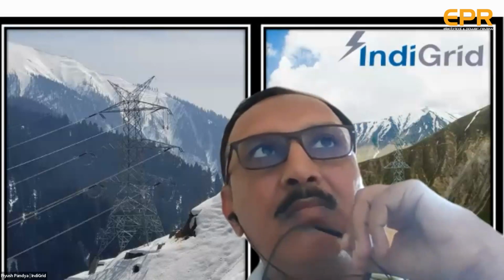Coming to sensorization, there are a lot of technologies available nowadays catering to various equipment. For equipment like transformers and reactors, online DGA, online bushing measurement, and monitoring controls are available. As well, in case of increasing water content, technology like online moisture removal is also available. So this can be employed on the equipment.